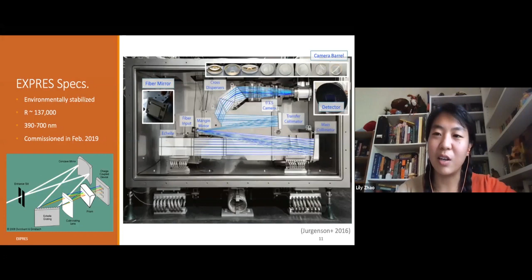So I'll go through some of the things that I think make EXPRES really cool. For example, the fiber mirror, the camera barrel, and also our detector. Our front-end module does actually a lot of the work for us. The front-end module goes on the telescope and guides the light from the telescope to the instrument. So it makes sure that the light from the telescope hits the spectrograph optics at the same place in the same way each time. So there's no variation from the light path. And it starts with this fast tip tilt mirror here, which looks at the image and makes sure that the fiber at the center of the mirror is always centered on the same part of the star.